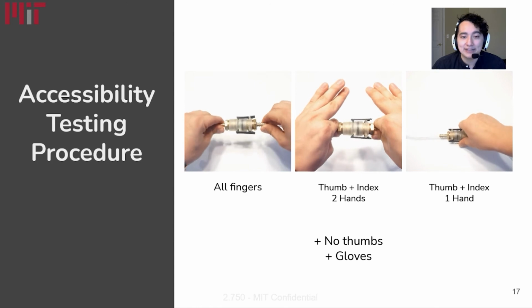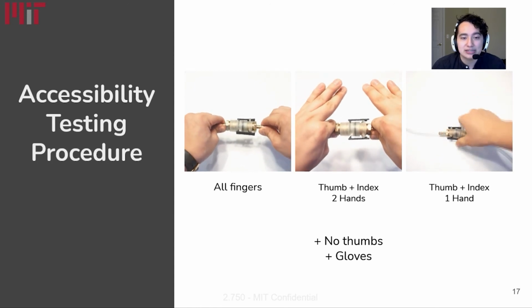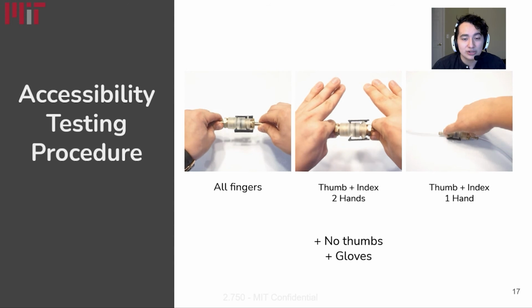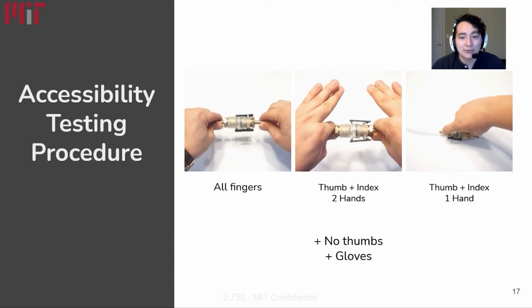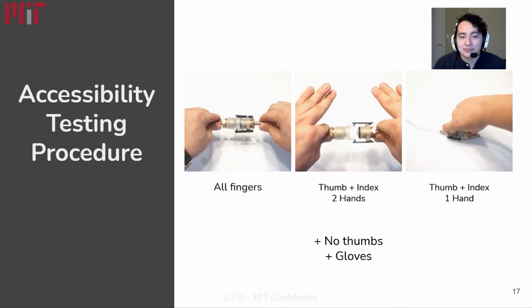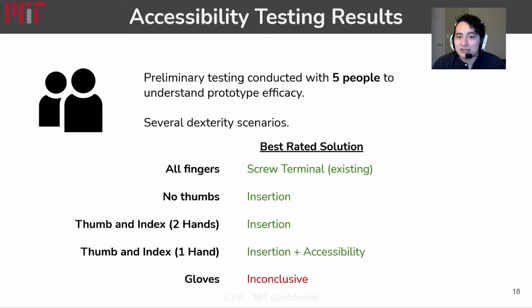In order to assess the efficacy of our connection system for making the connection process easier, we tested the existing solution, our insertion solution, and our insertion solution with the accessibility mechanism in a variety of dexterity scenarios. What we found through this preliminary testing is that the existing connection solution works best when users were unimpaired. However, as users begin to lose dexterity in these scenarios, they found our insertion mechanism easier to operate. As they got to the extreme end of dexterity loss in the one-hand scenario, our accessibility mechanism became almost necessary for users to feel secure during the forming process.